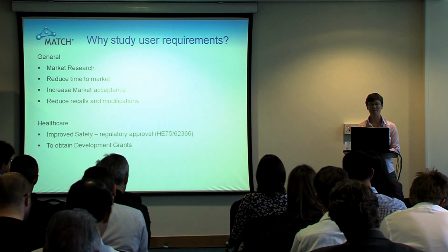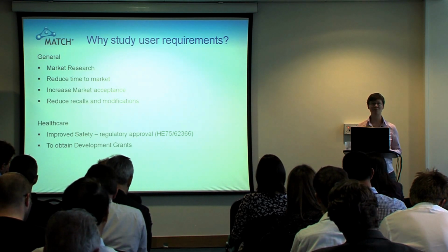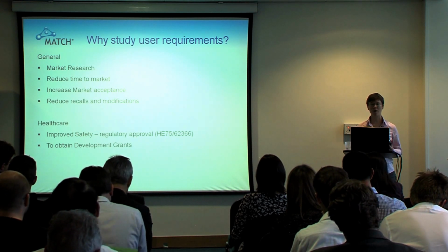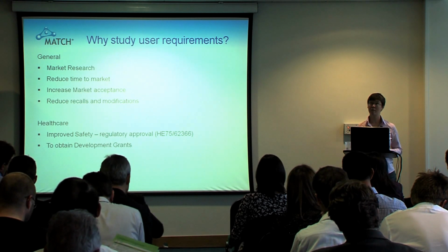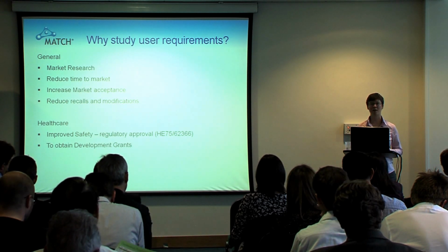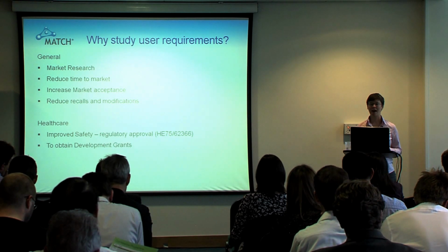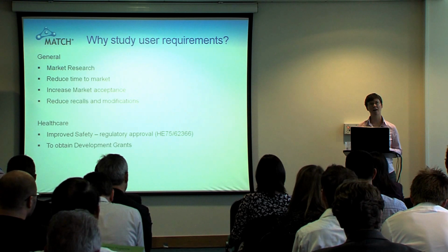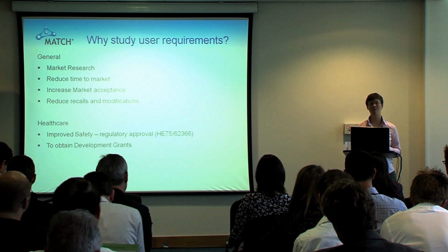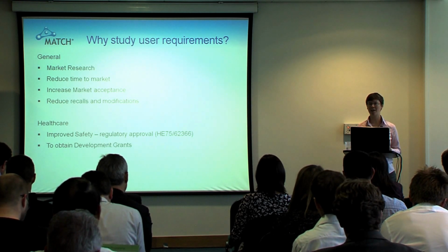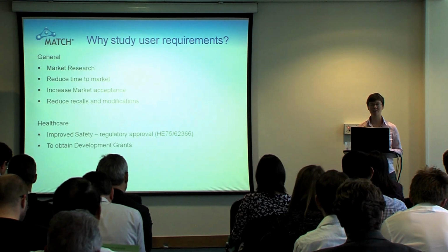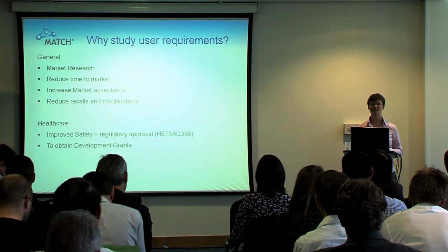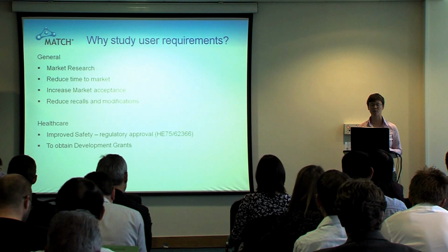has been really interesting for me, and seeing some of the submissions that come from manufacturers and where manufacturers are frustrated with the guidance that's out there at the moment, and struggling to demonstrate all the work that they've done, and sometimes not realising how much work they have done, and only submitting information on final usability tests rather than the earlier research which the FDA wants to see.